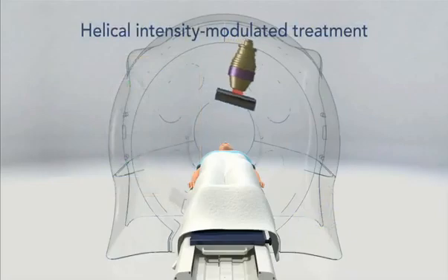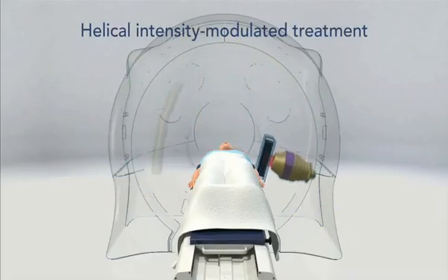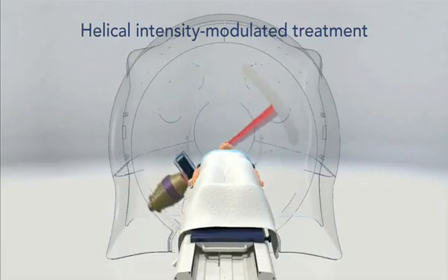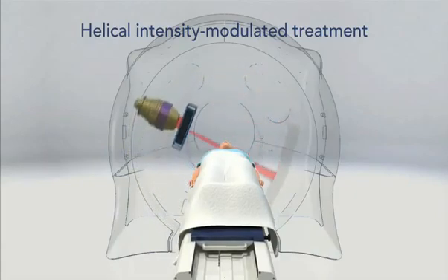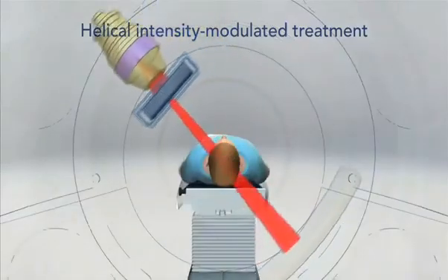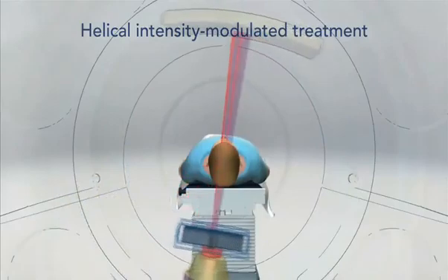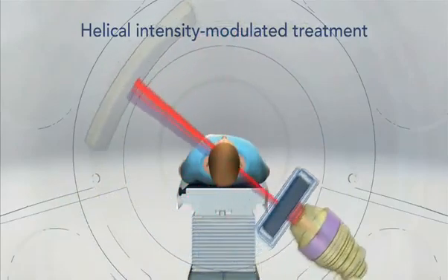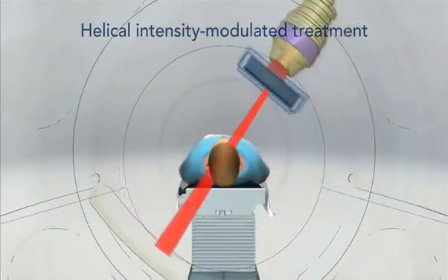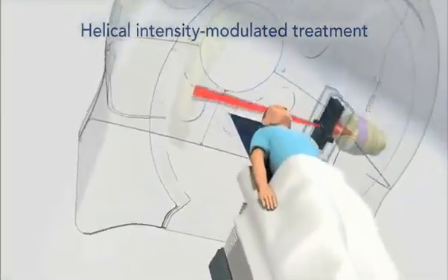For treatment delivery, the same helical rotations of the X-ray beam source are used. This time, however, the intensity of the beam is changed rapidly during each rotation, according to the shape of the tumor, using thin tungsten leaves that block or unblock the beam. The 64 leaves in our unique binary multileaf collimator create tens of thousands of optimized 6-millimeter-wide beam elements known as beamlets.